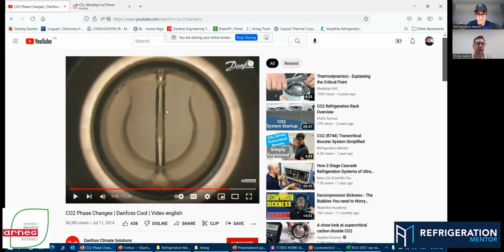It's going to pass through a high pressure expansion device. Imagine that high pressure expansion device is just like your thermal expansion valve that you've always been working with, but naturally it's operating at high pressure and has a lot of mass going through it. So part of that mass that's going to be produced is flash gas. Flash gas has always existed in evaporators. Anything as you're flashing down through your synthetic refrigerant into an evaporator or your CO2 system, it's a byproduct of being produced. But hence, we're taking the whole system, running it through that device. We have a substantially greater amount of that flash gas being produced.